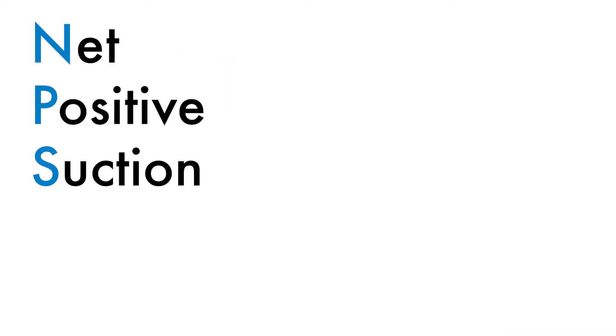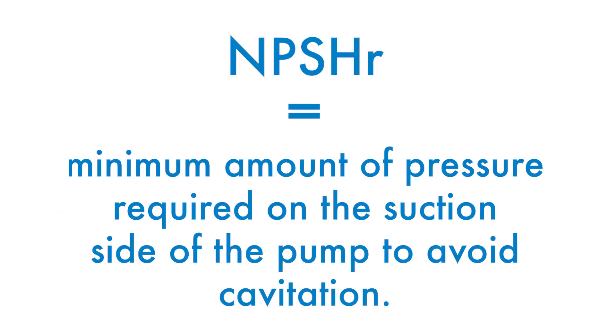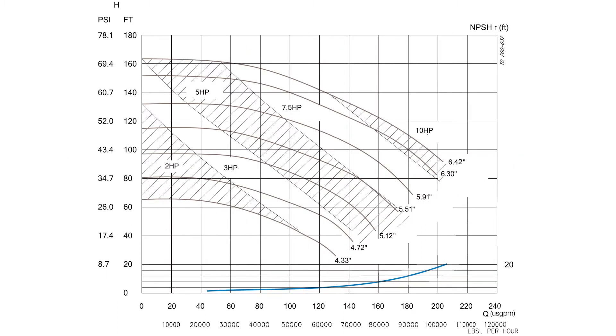which stands for Net Positive Suction Head Required. NPSHR is the minimum amount of pressure required on the suction side of the pump to avoid cavitation. NPSHR is determined by the pump as each one is different.